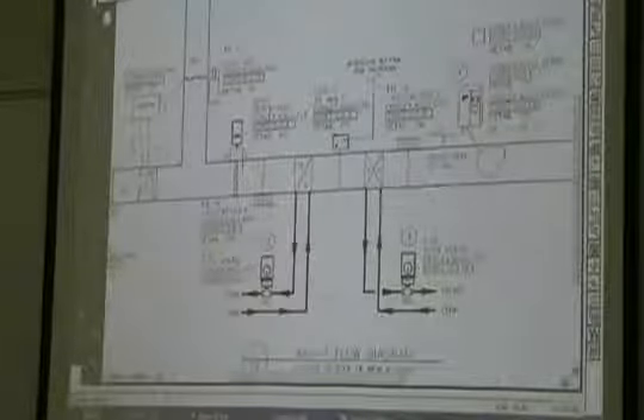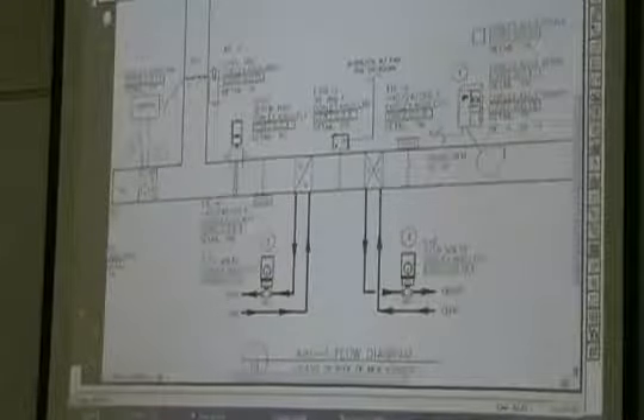Talks about also that this low temp detector is going to be a manual reset. Talks about a bunch of stuff in here about if different temperature sensors have failed, what we do, and that's really confusing. That's getting into a lot of detail that we usually don't see. But it says stuff like if this temperature sensor fails right here, then we go to just an airflow control over here. Just go to a minimum. Whatever. If the supply air temp sensor fails, we do something different. If we have time, we'll go back and go into that in detail. We'll skip that for right now.